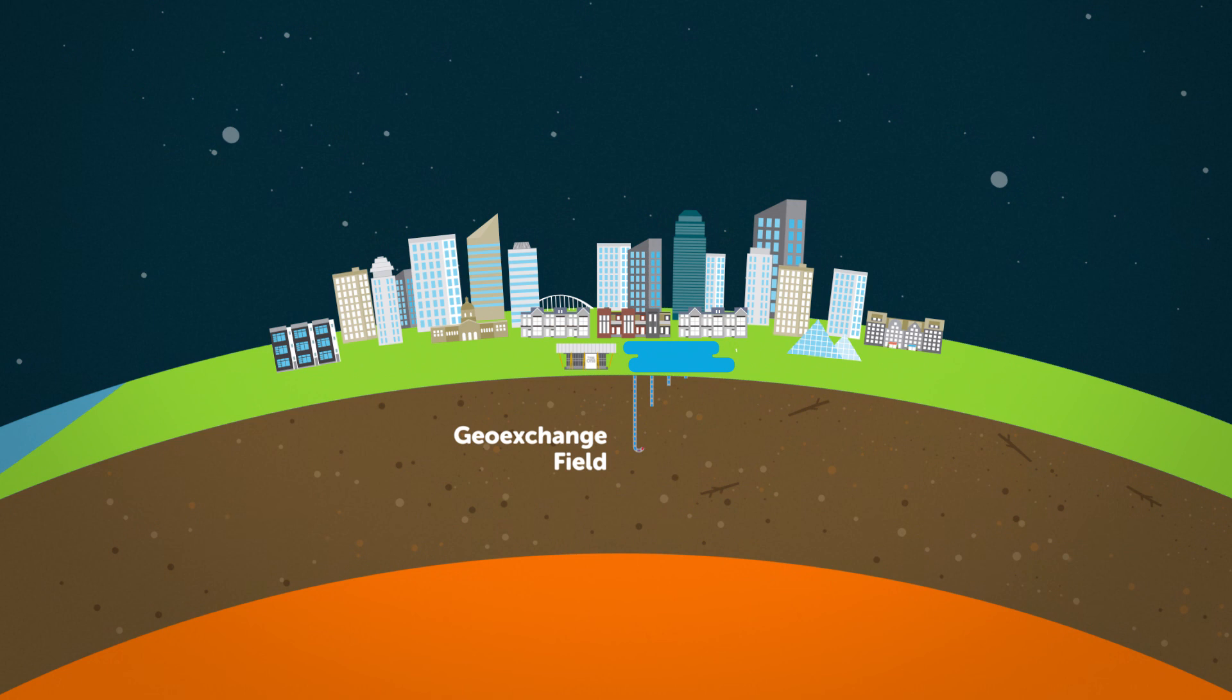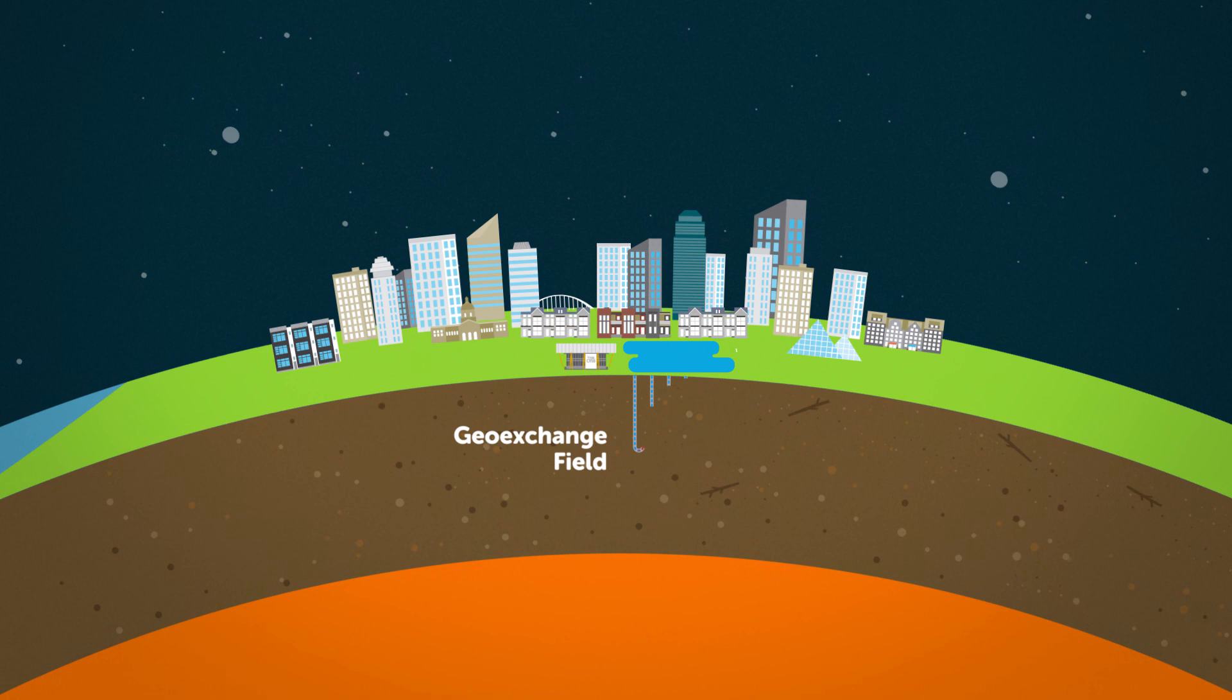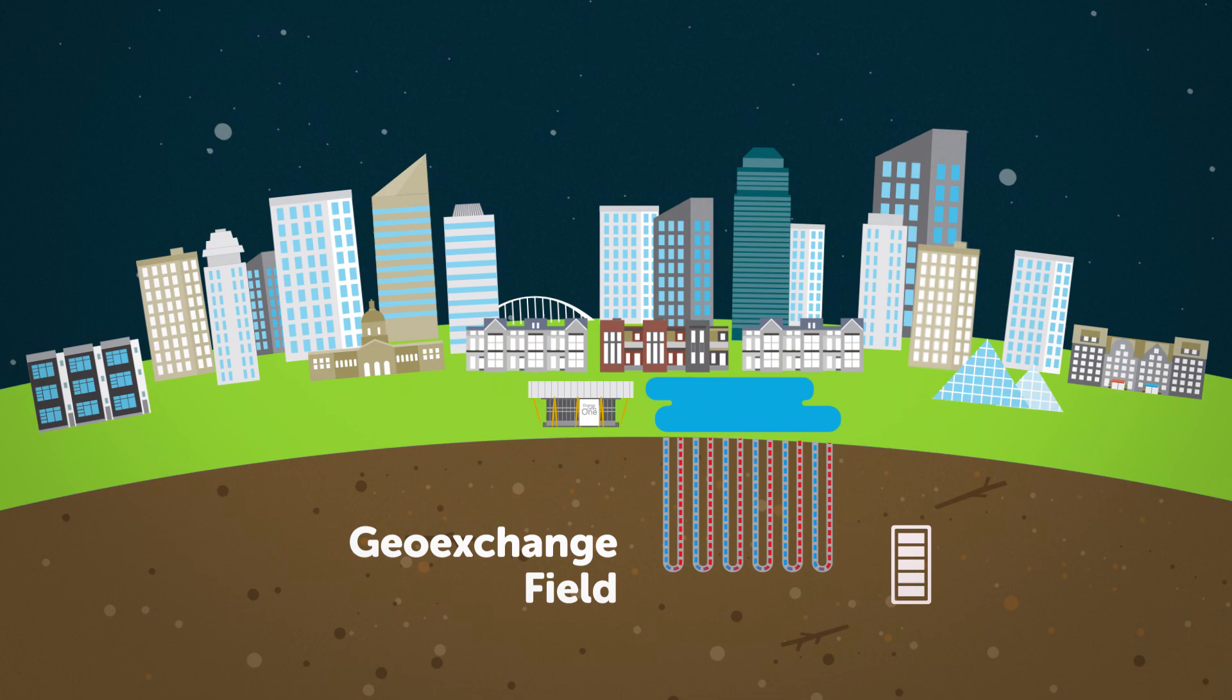To access this renewable energy, we've built a geo-exchange field by drilling boreholes 150 meters into the Earth, where the temperature is always around 8 degrees Celsius, even in winter. This geo-exchange field is like a massive ground energy battery that charges the district energy sharing system.